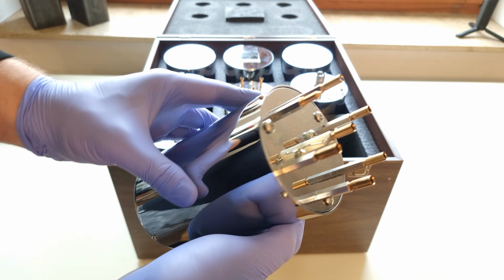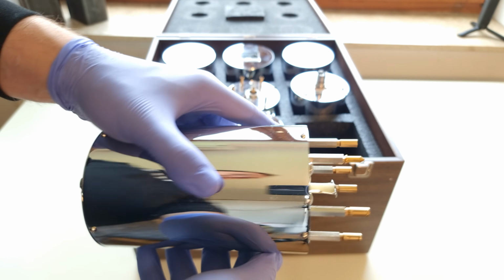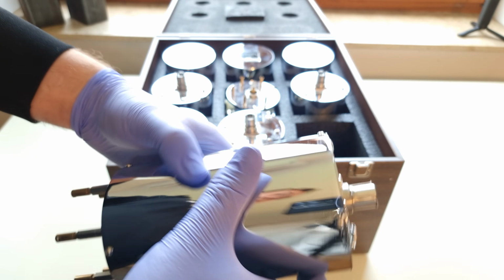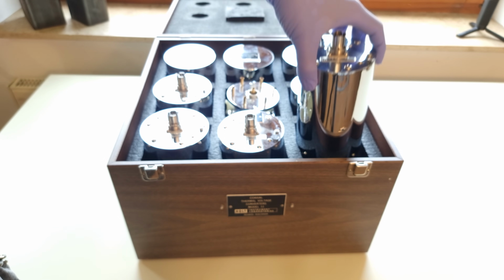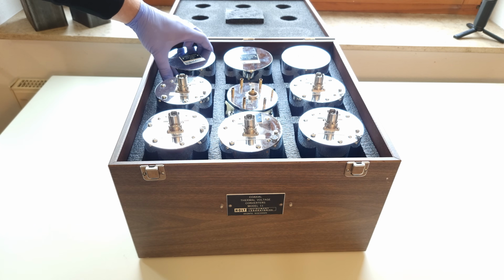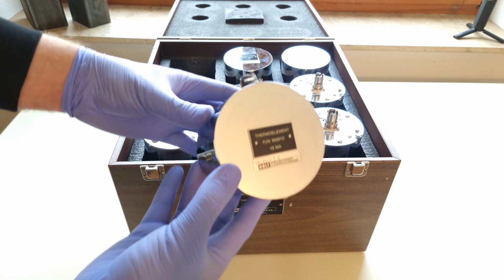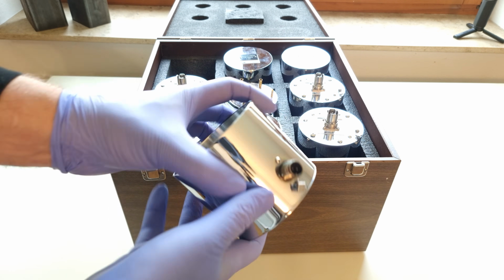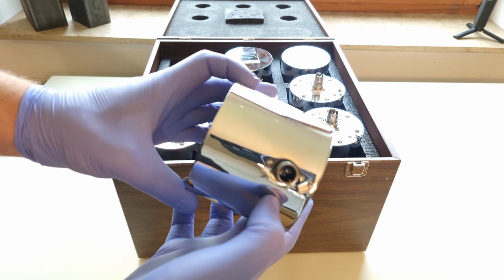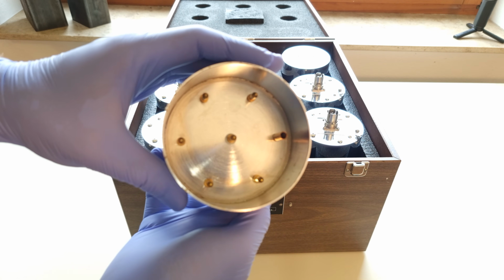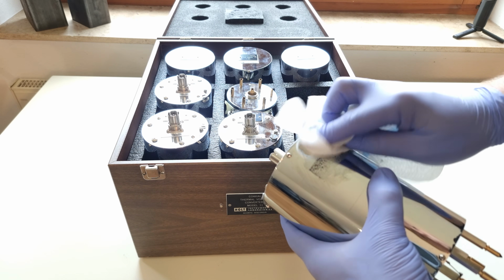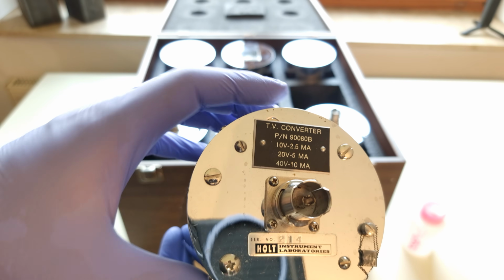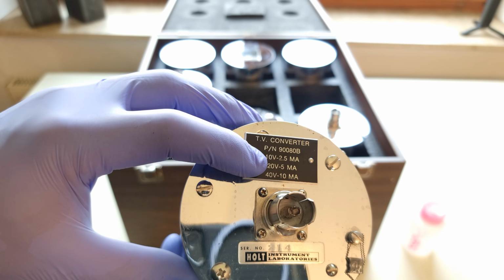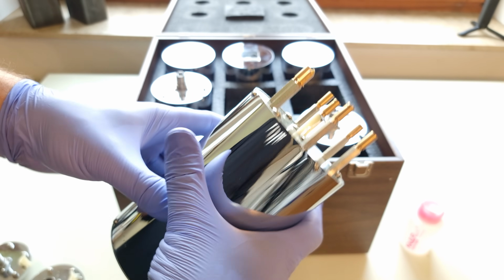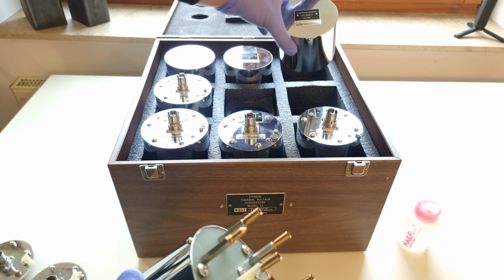It basically consists of 5 resistors and 3 actual current input thermocouple output converters. The one and only purpose of a venerable system such as this is to make RMS comparisons, i.e. put in one signal, measure how much temperature it generates, and then replicate that temperature with another signal such as DC voltage, which would then be its RMS representation. Let's try and use this to figure out who's responsible for the kink in Datron's ACV linearity. Each resistor comes with suggestions as to what converter to use for what voltages. Through combinations, a wide range of sensitivities between 3 and 1200 volt are covered.